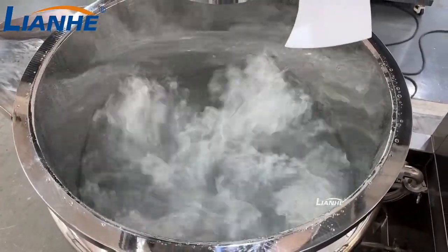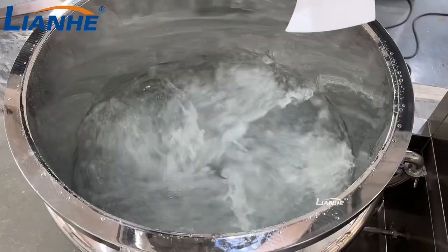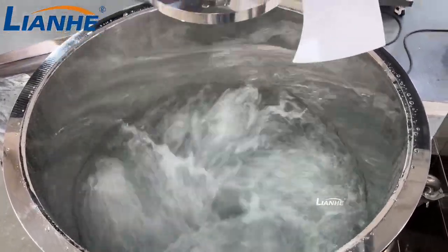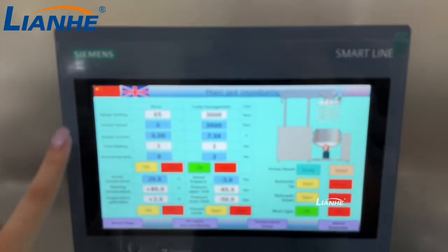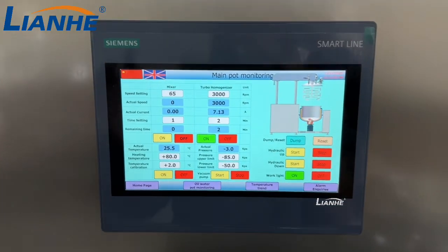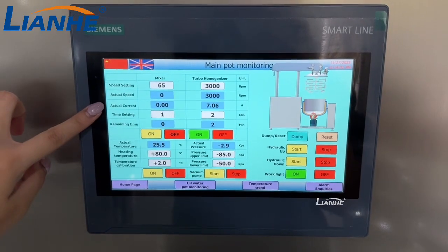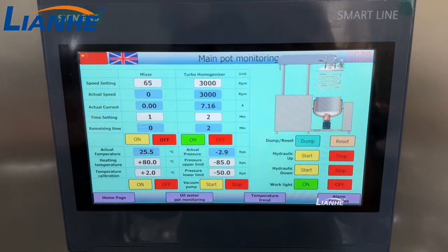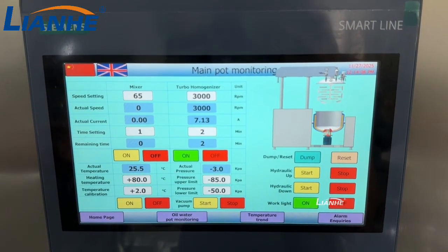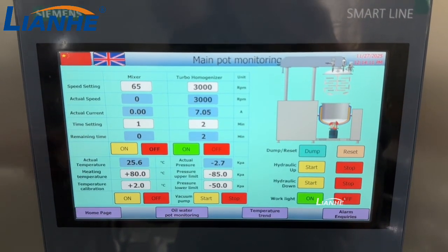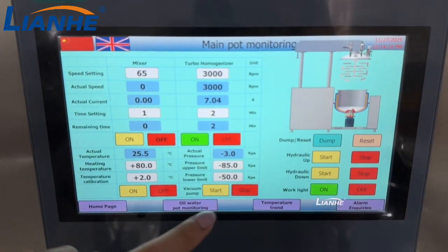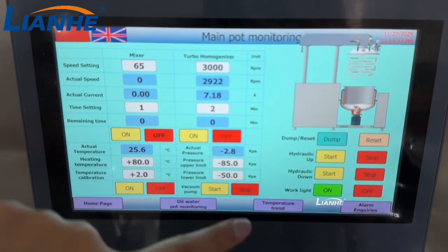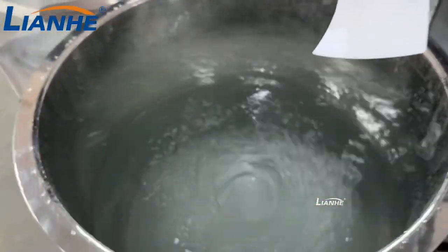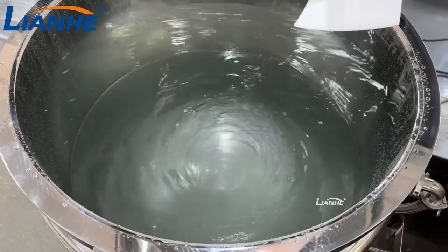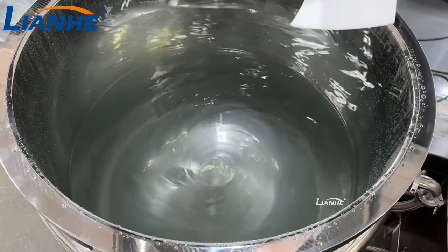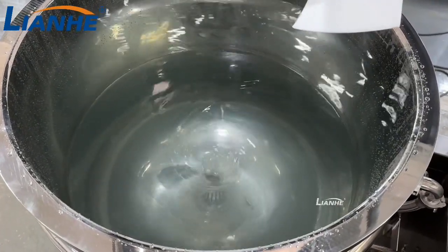Now you may check the homogenizing function is working. And the actual speed is now 3000, and the actual current here. And it's the same as the mixing function. If you set like 2 minutes, when the time arrives at 2 minutes, it will stop automatically. And now we can manually turn it off. And now the homogenizing function is stopped.